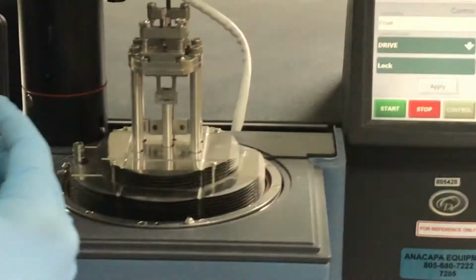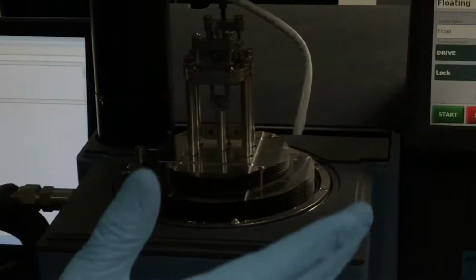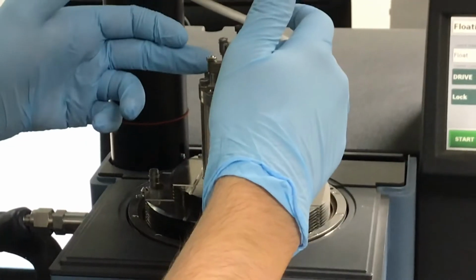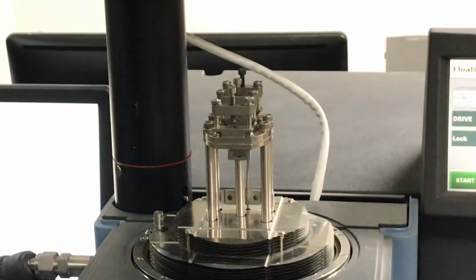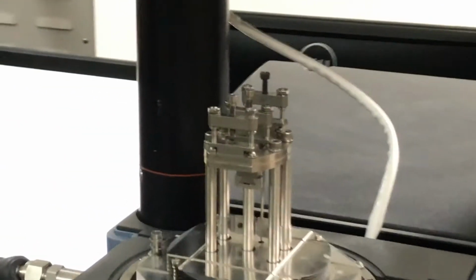We want to do all calibrations, so that's going to include the clamp mass calibration. So basically what I'm going to do is start it up, and there's nothing going to be connected onto it, because it needs to calibrate the mass of this clamp right here. So let's go ahead and get that started.